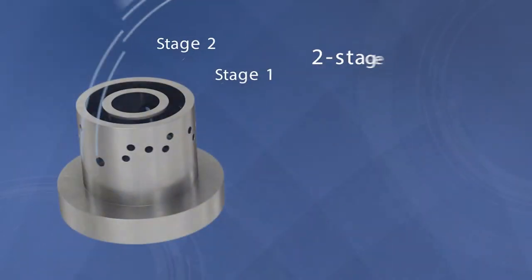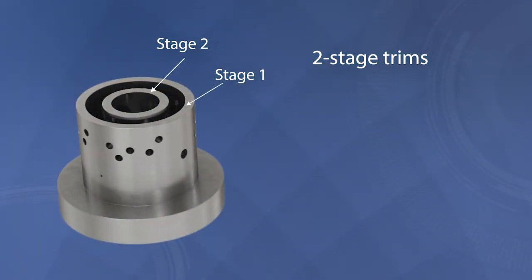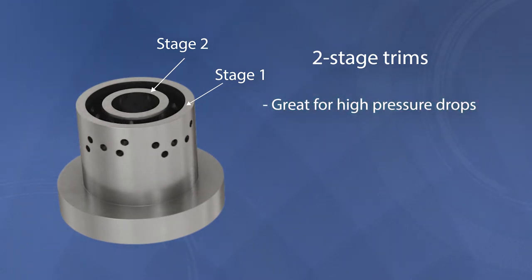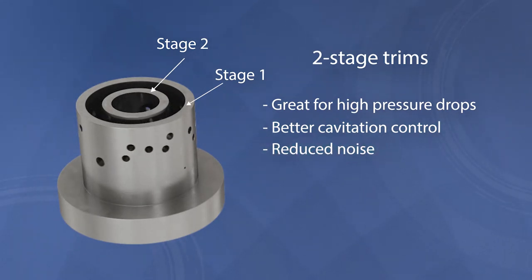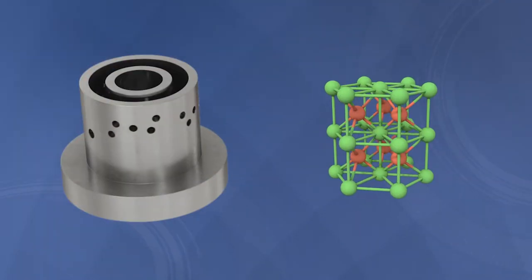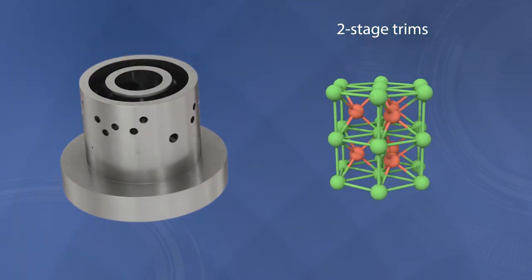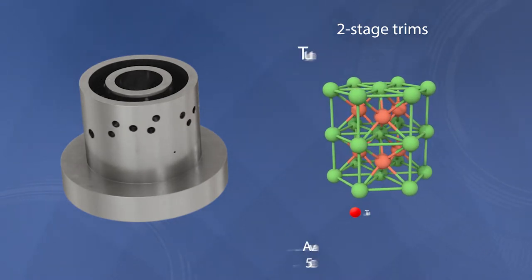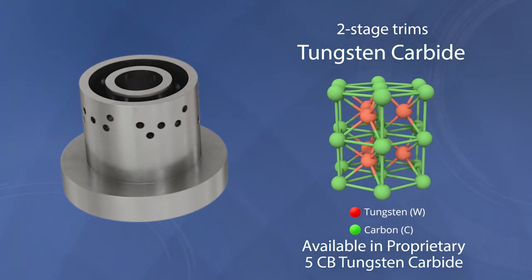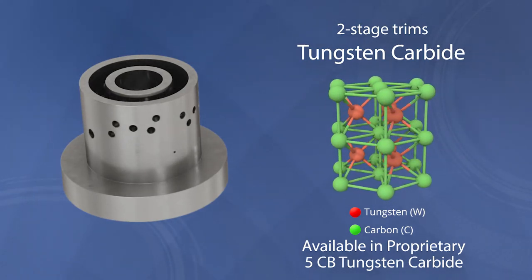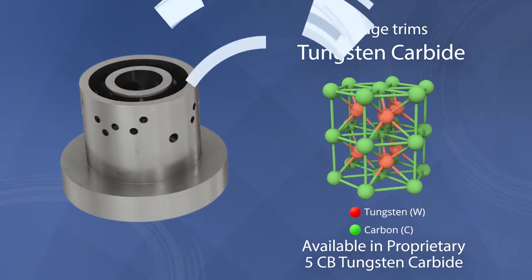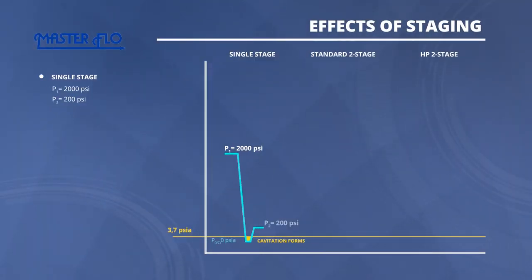For demanding applications with high pressure drops, two-stage trims can be used. They consist of concentric cages which handle pressure drops in stages, reducing the pressure dip at the vena contracta. This results in better control over cavitation and noise. Master Flo's multi-stage trims are available in service-specific materials, including the proprietary 5CB tungsten carbide, for higher erosion and corrosion resistance. Multi-stage trims can also be engineered to provide custom flow curves, and the effects of staging can be seen on these graphs.